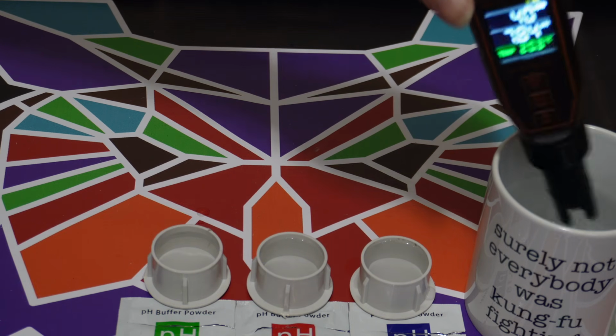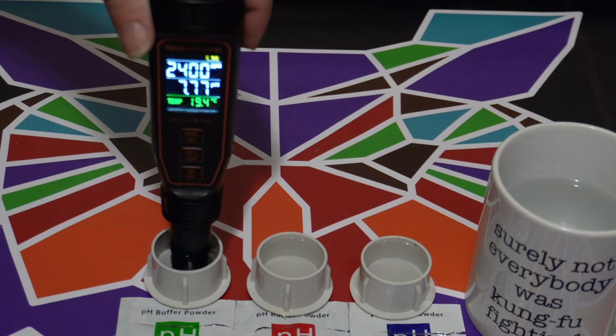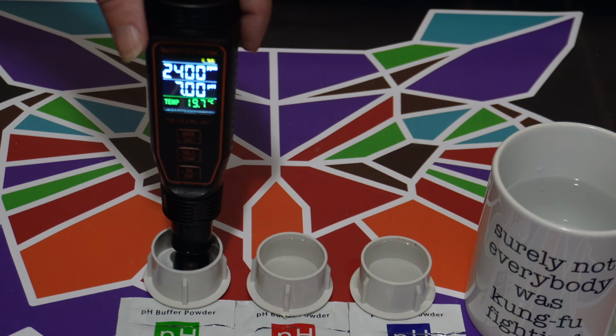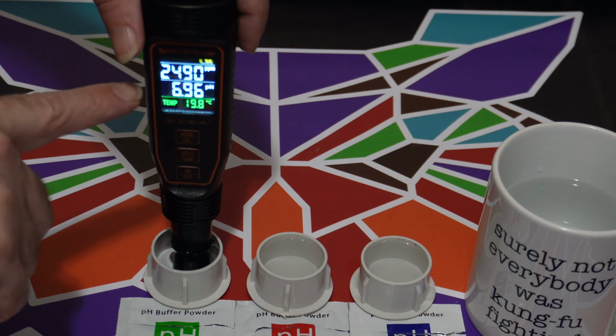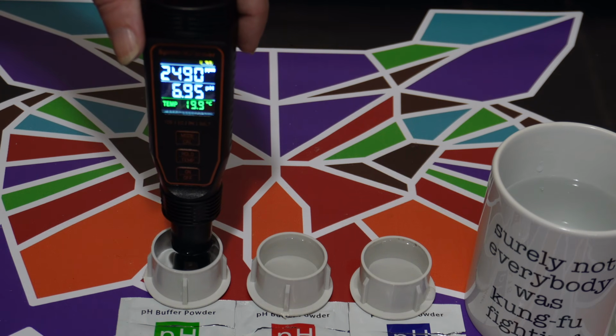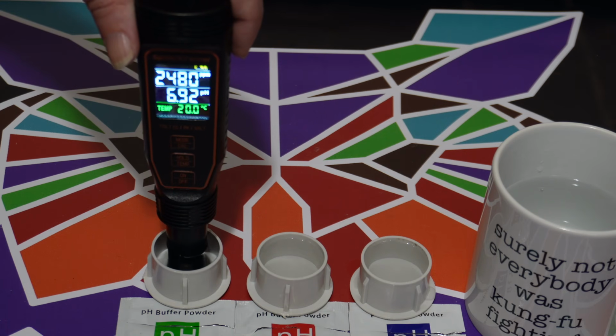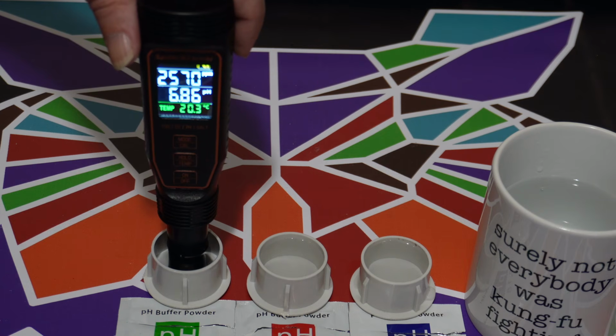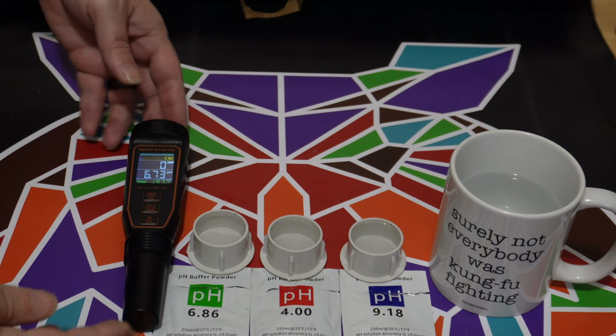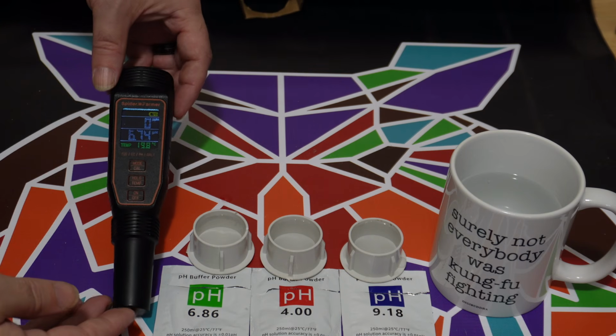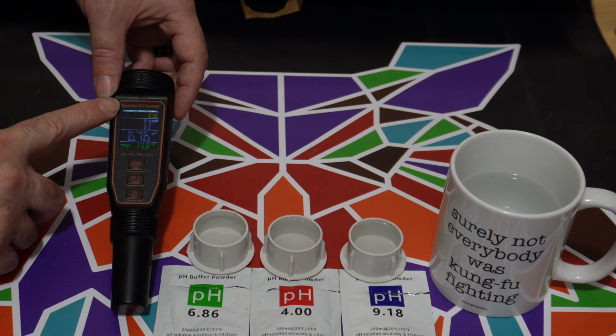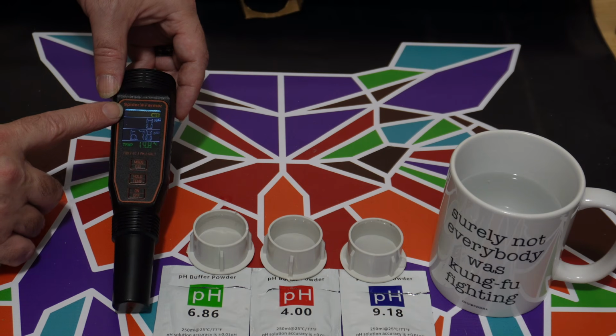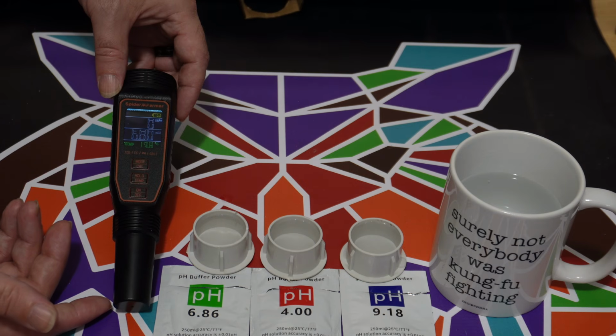Rinse it off. I'm not going to dry it off. Go back into our 6.86 solution and let's just see where that is coming in at now. It's going down. See if it gets back to that 6.86, which is what we would expect. Okay, there it is, that 6.86. All right, guys, so this is the pH EC TDS pen from Spider Farmer. Check your water, check your nutrient solution. This pen will do that for you.